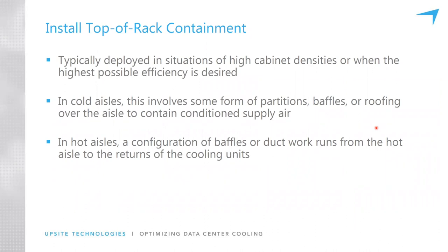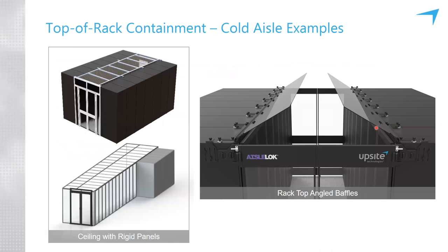Let's talk about the top of the cabinets. So in high density situations or challenging architecture, in rooms where there are low ceilings and the placement of the cooling units means that the airflow path back to the cooling units is quite turbulent, it might be necessary to install some containment across the tops of the cabinets, either baffles or a full roof of some sort. So in this example, there's a full solid roof, and these happen to be drop-away panels that in the event of a fire, become warm and lose their structural integrity, and they just get kind of gooey and drop out. And that would be the case in this example as well, this quite wide aisle.